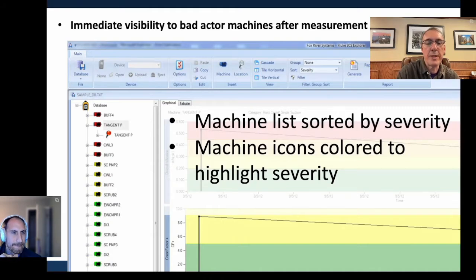Great question. We only have really a means of assessing that based on the choice that a user makes to describe their machine as one of the 37 supported machine types. In other words, not selecting other. Because with every one of the machine categories, there is an acceptable range of vibration levels. Based on overall vibration, so not looking at crest factor then.